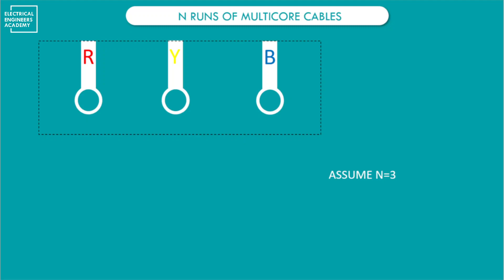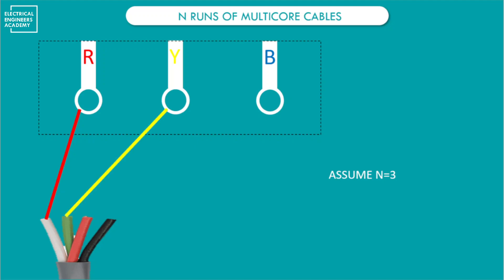For multi-core cables, we need to understand how the cables are connected to the terminals. I have drawn here three terminals — these could be a motor, or any type of load that has three terminals: R, Y, B. This is the first cable run — a four-core cable. The first core connects to R, the second core connects to Y, and the third core connects to the B terminal. This represents a single run.